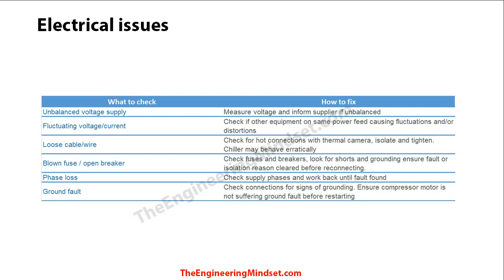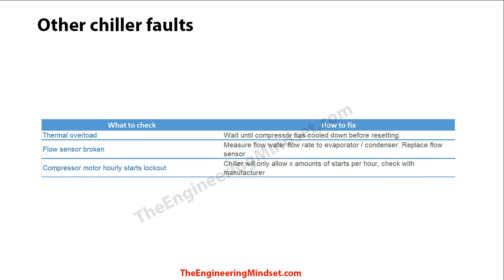Phase loss is also possible — if one phase of a three-phase supply has been lost or disconnected, the chiller will not start. There could also be a ground fault in the motor; the chiller will detect this and shut off for safety. Do not turn it on if a ground fault is suspected, as this can be very expensive to fix. Thermal overload is another cause — if the motor casing temperature gets too high, the chiller will cut out and will not restart until the temperature drops below the threshold.